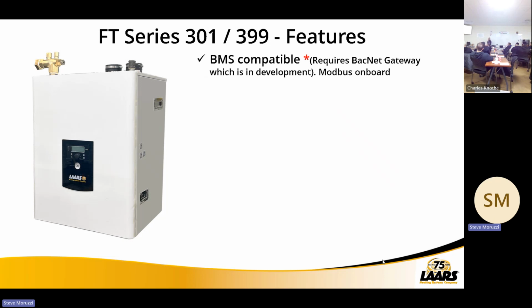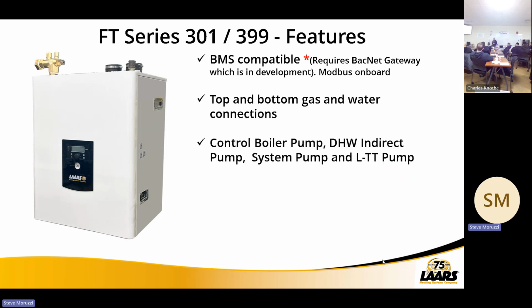So BMS compatible. Top and bottom connects. So you can either connect your piping gas off the top or the bottom or both. Okay. So example, I've got a hydronic heating loop and I have an indirect tank. I can take my hydronic heating maybe off the top and the indirect tank off the bottom. Okay. And I can mix match those as well.